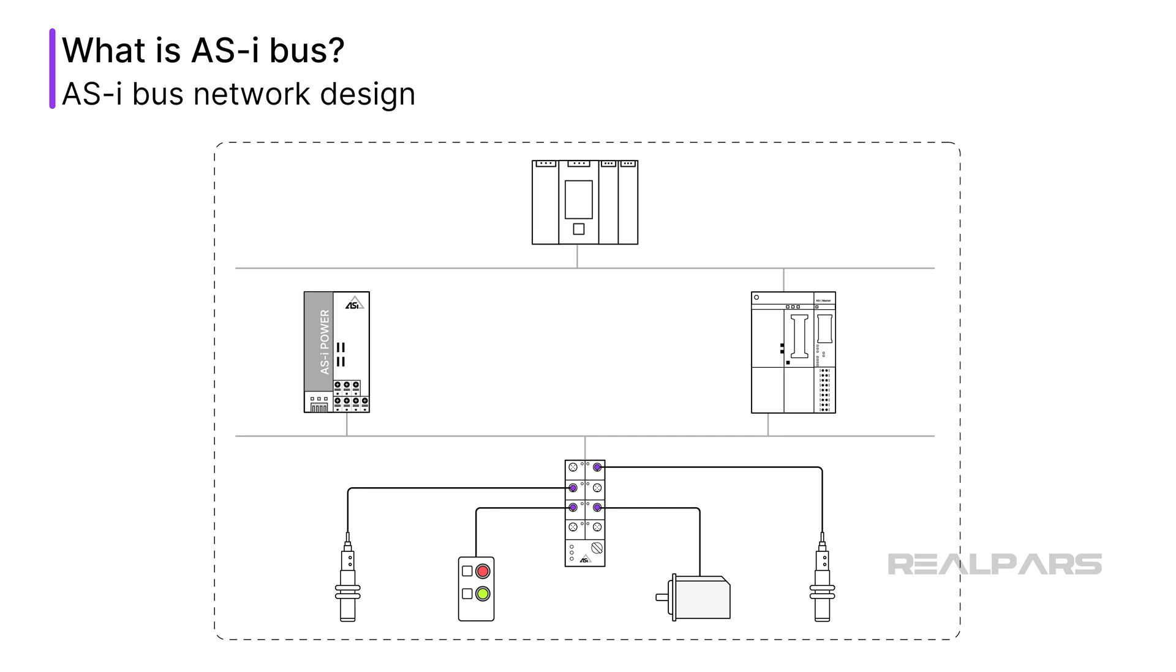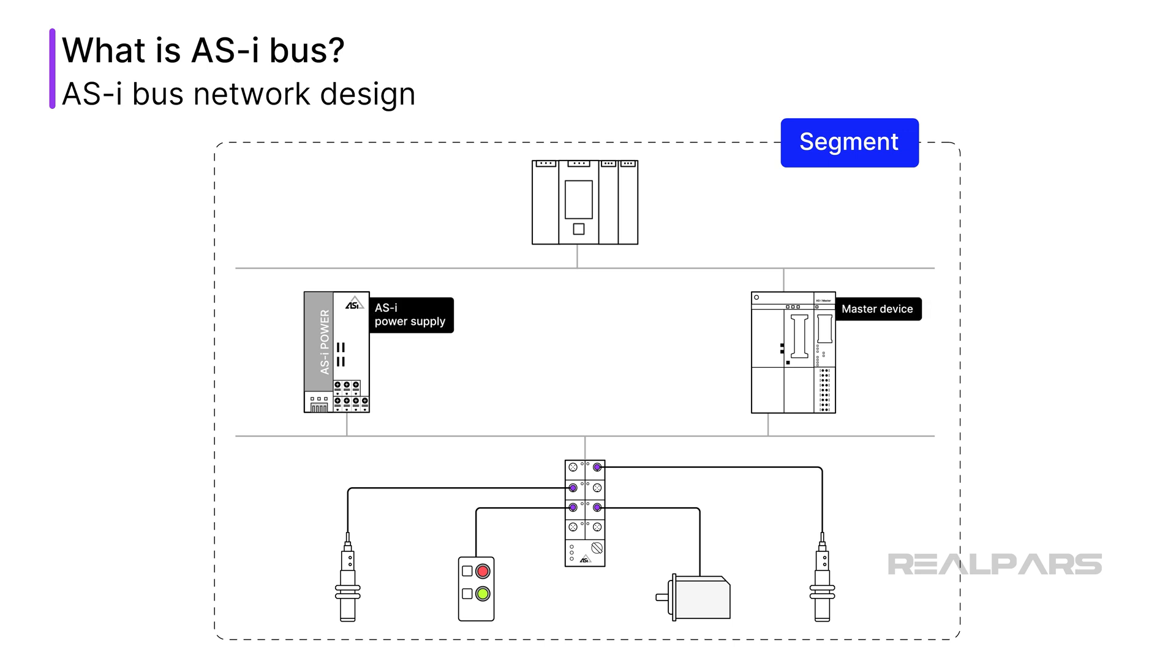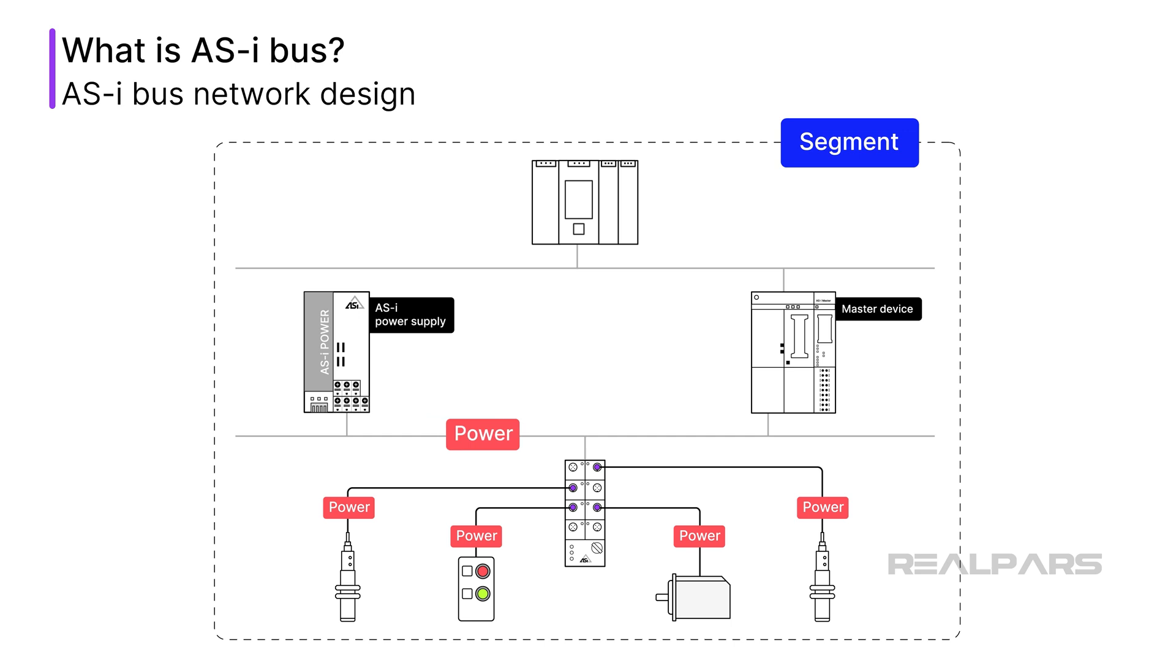AS-i bus networks are divided into segments. Each segment can be thought of as a length of cable from which devices like controllers, sensors, and actuators are connected. Each segment must contain what is called a master device and a power supply. The master device is used to manage, direct, and control communication over the segment. The master sends commands to the connected devices and receives data from them. The power supply provides the power for communication as well as to power the individual devices.